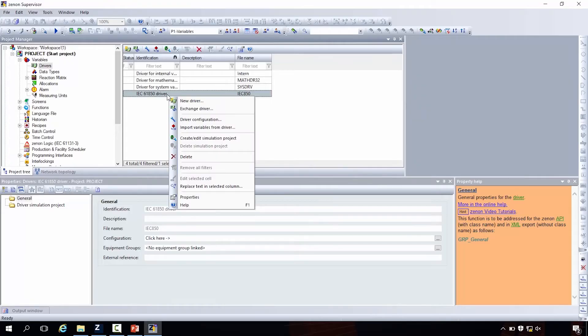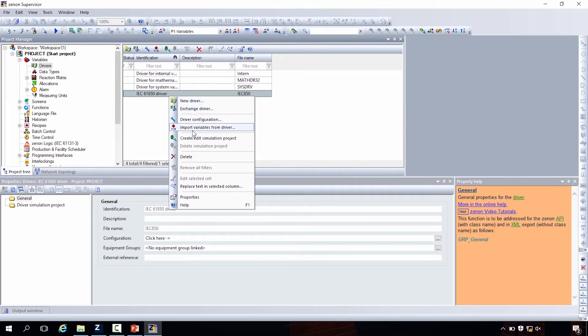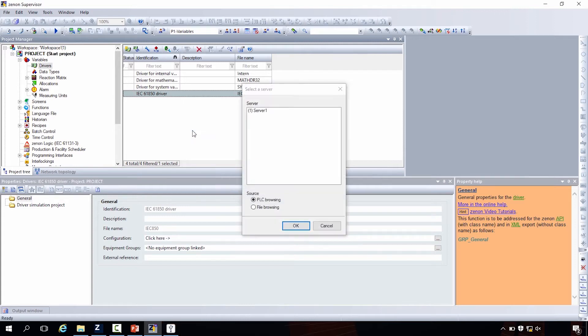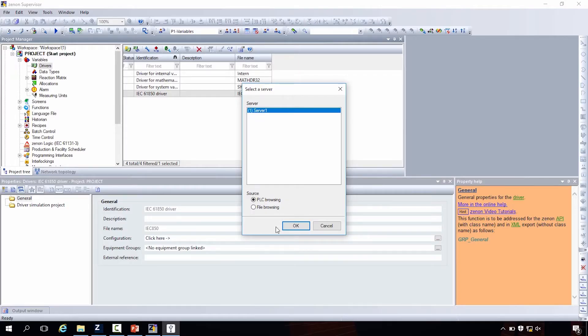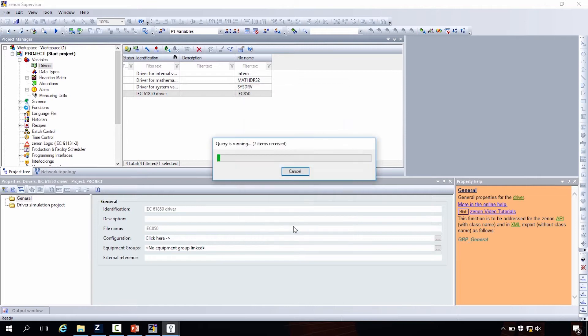Actually this driver offers an import possibility, online or offline import. We have the device here. We can choose the online import. With a right click on the driver, you can select here import variables from driver. You have the choice, either the PLC browsing directly from the device online or the file browsing from the file. I select the server, the connection we just created. The driver directly browses the object model in the server and gives us all the information, all the tags.